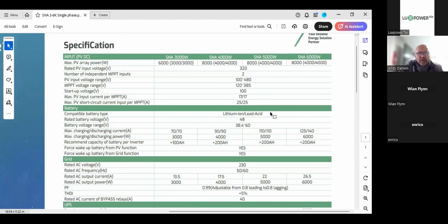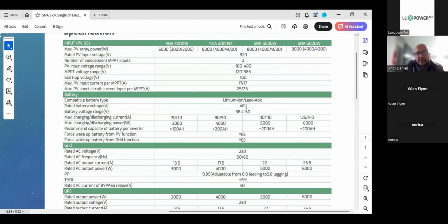Okay, while I've got this open, let's just have a look at battery types. The battery types are lithium and lead acid. Now, lead acid is obviously old terminology, so we should actually just change it to voltage control, because there are guys that are using batteries that are not on our list, or you're still using the old gel batteries, or you might be using an old lead acid battery. It can accept any one of them. The nominal voltage range is 48 volt. Obviously, we can operate from 38 volt up to 60 volt. All right.